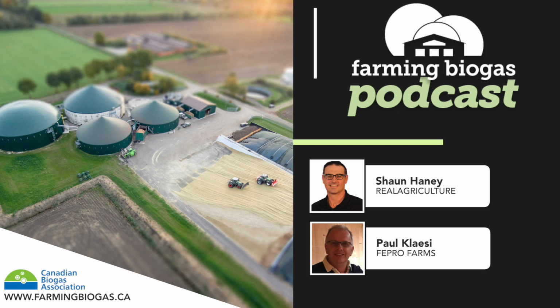Then the second thing we do is the actual cooler of the engine, of our 500 kVA engine, is installed between grain bins, between dryer grain bins. So we don't use energy anymore to dry. We use the heat from the generator to dry corn and beans. So we can dry about 350 ton in 10 days, roughly, and then we have to move it over and fill it again. So it saved us some money, and we also heat the calf barn, the milk house, 2 houses, and a large workshop.